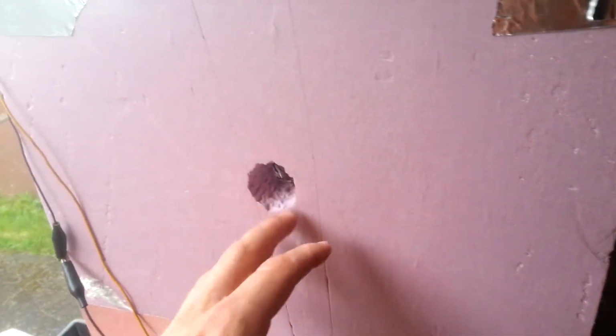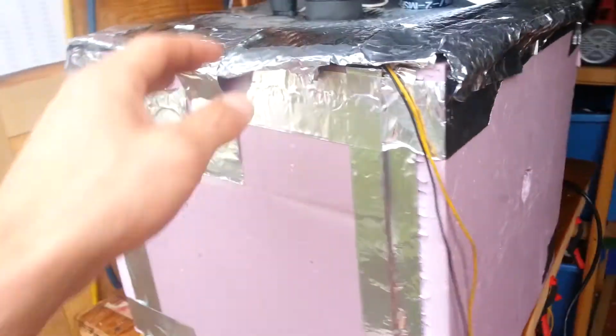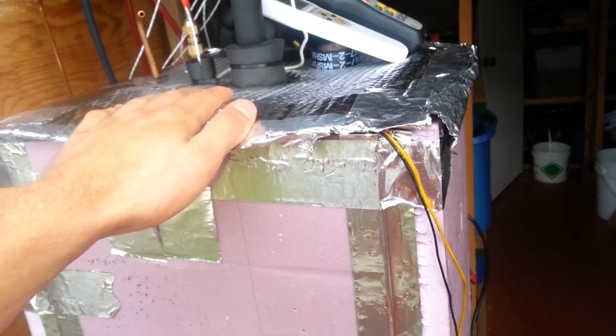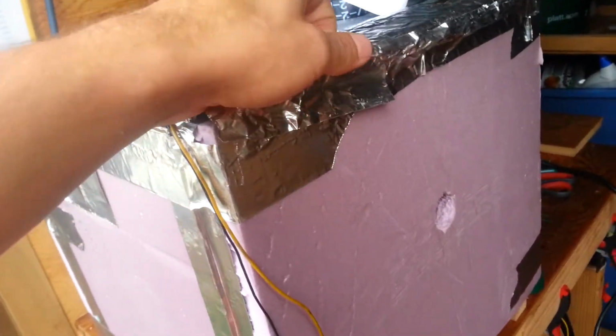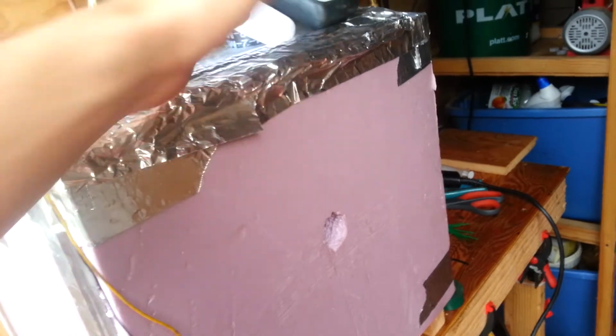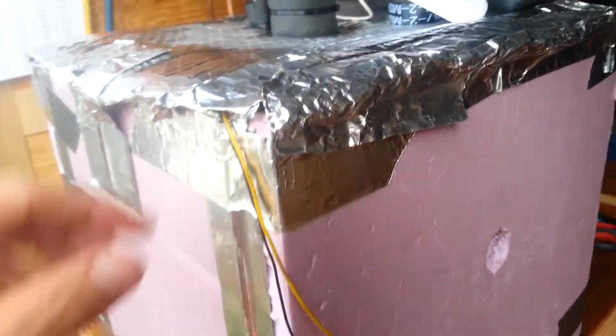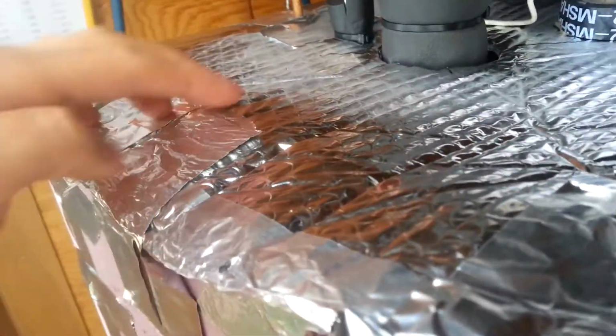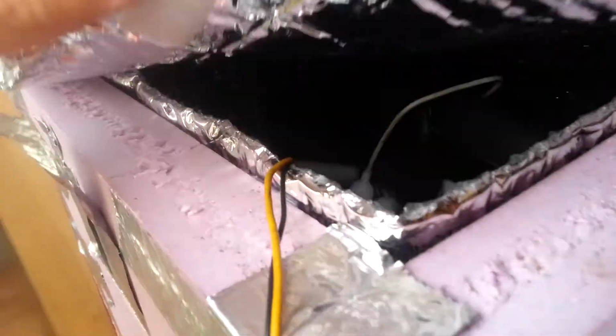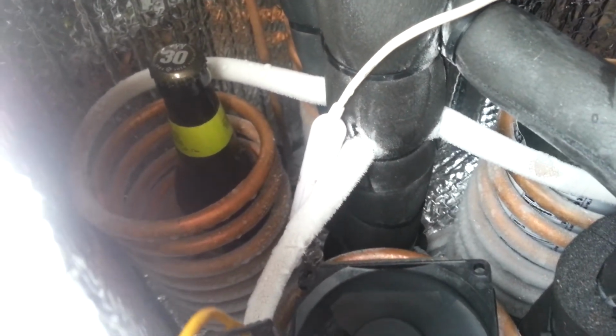Now the box is going to get changed eventually. This thing's an ugly piece of shit, and the entire evaporator, I'm going to build a new one, one that actually chills, makes plate ice, because there are also some issues. I mean, there's poor surface area in here. The fan helped substantially, but I don't like the fact that there's such long runs of coil in there. So the next evaporator is actually going to have pretty much vertical coils. You get a lot more brazing, but good heat transfer to make ice.